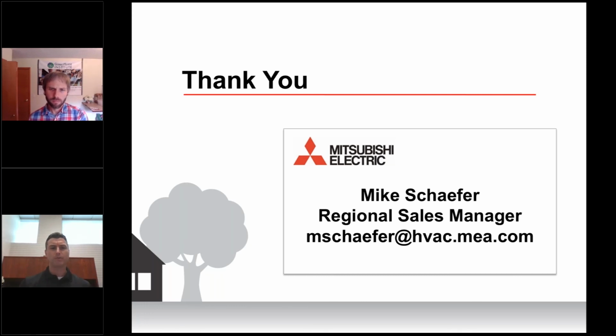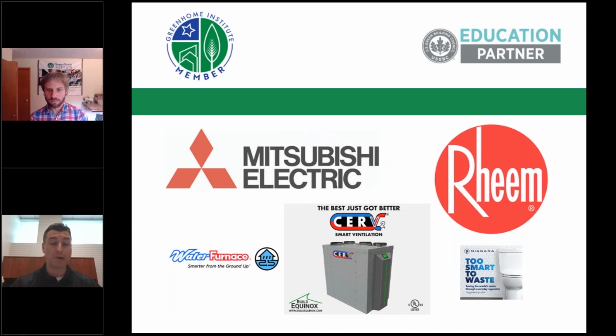Dual fuel systems have been around forever. It's not new. I was a contractor, and when I worked for a contractor, I installed dual fuel heat pump systems. The problem was you were setting balance points at like 37 degrees. Mm-hmm. Well, you're spending so much, you're not really getting the most out of that heat pump. By incorporating the cold climate heat pump technology, which is going to be the big key factor, you're going to be able to take that balance point down to say 0 or 5, depending on what you want to accomplish, to really limit that natural gas or propane, that fossil fuel usage in general. Let the heat pump take the brunt of the heating season.